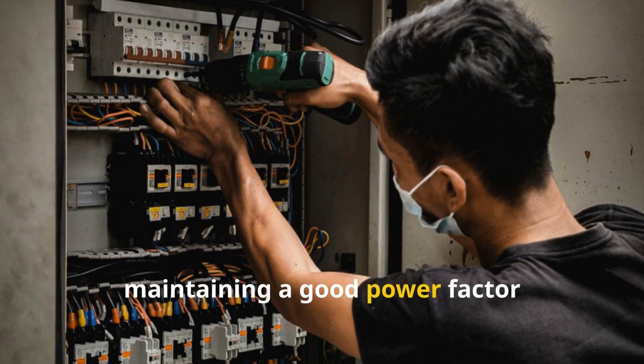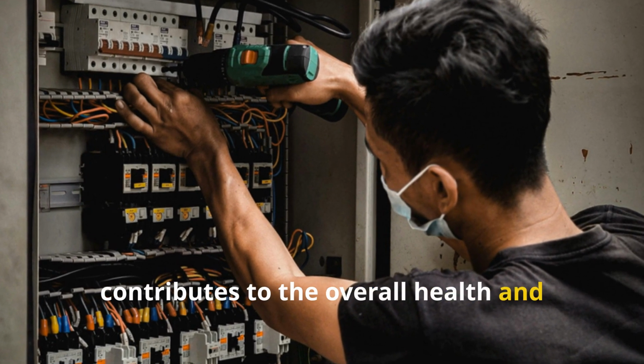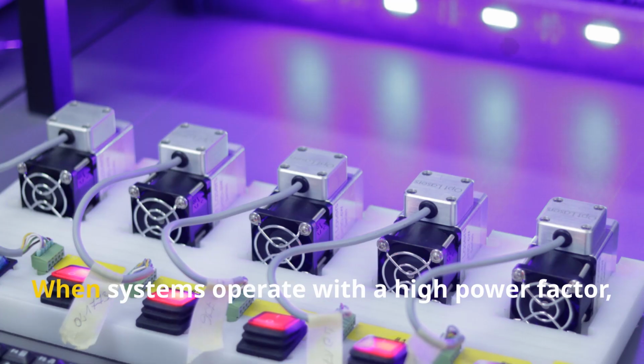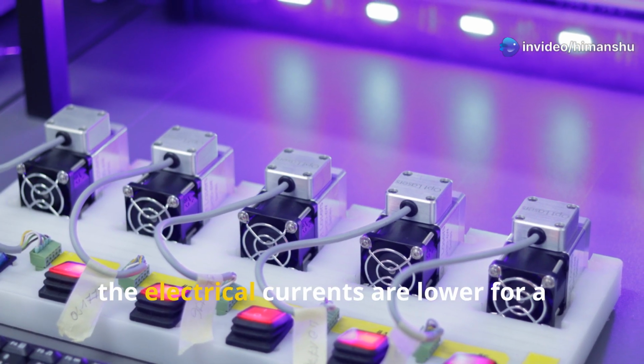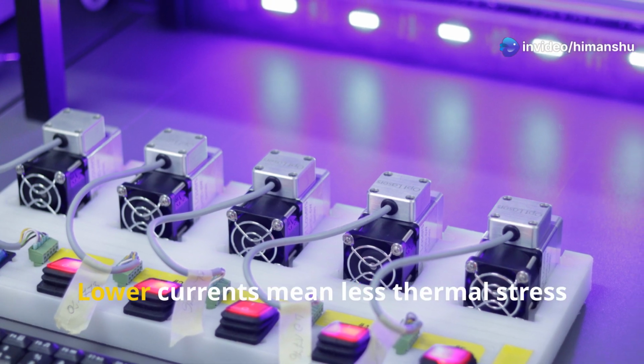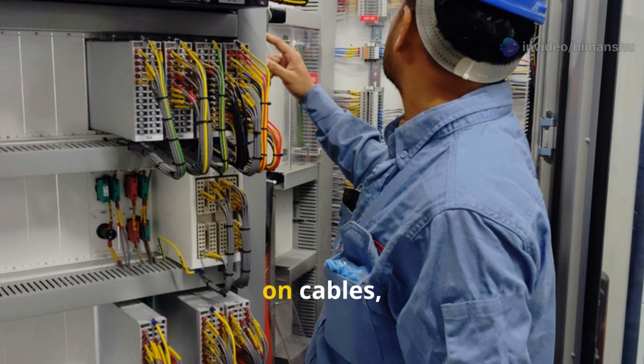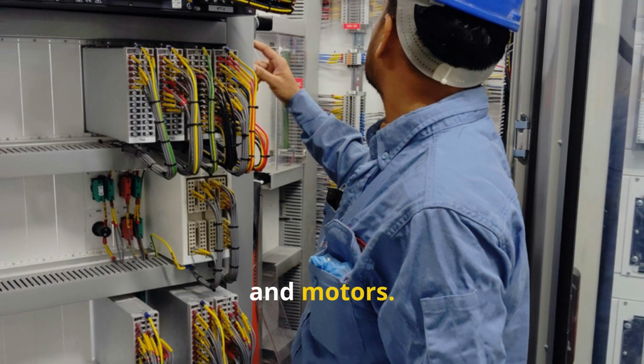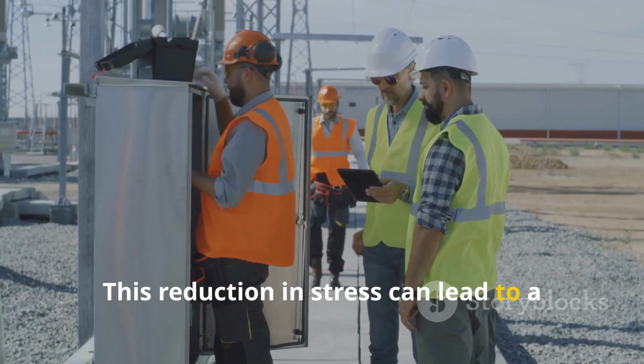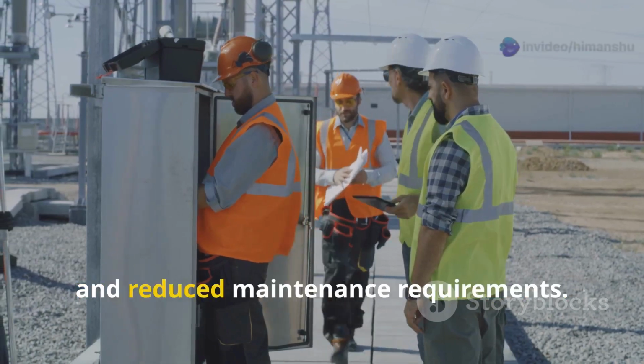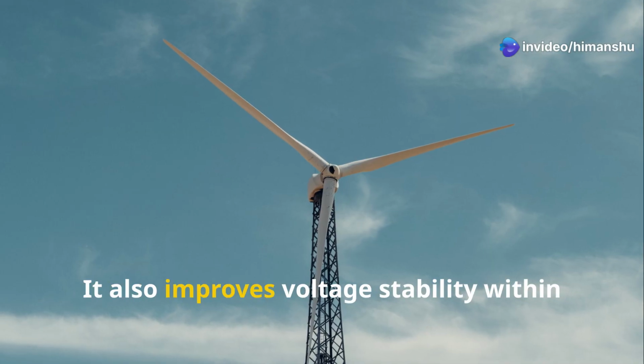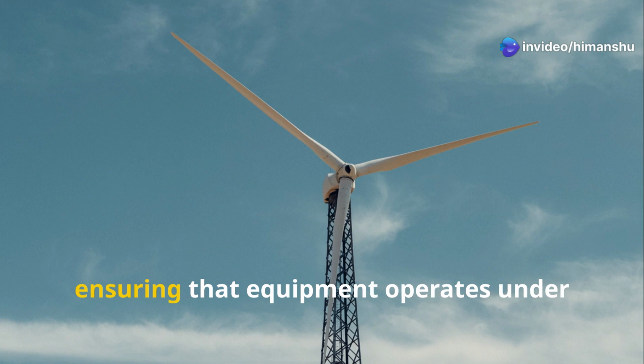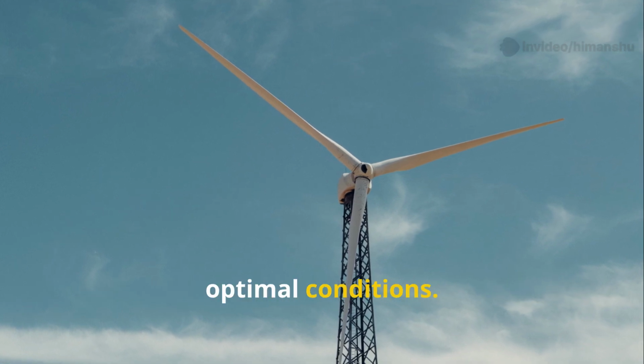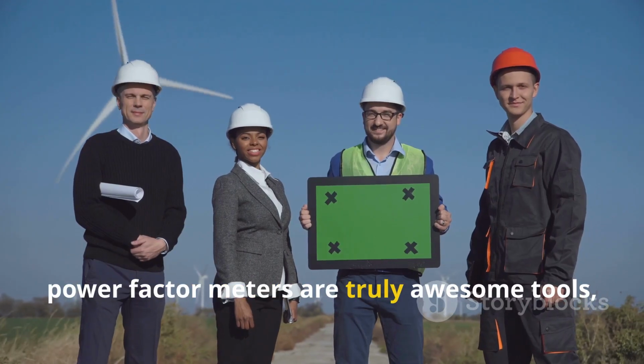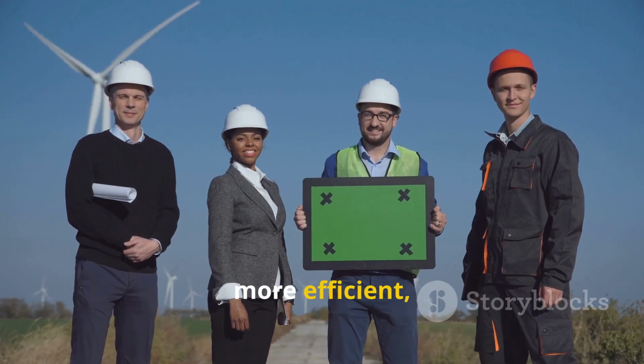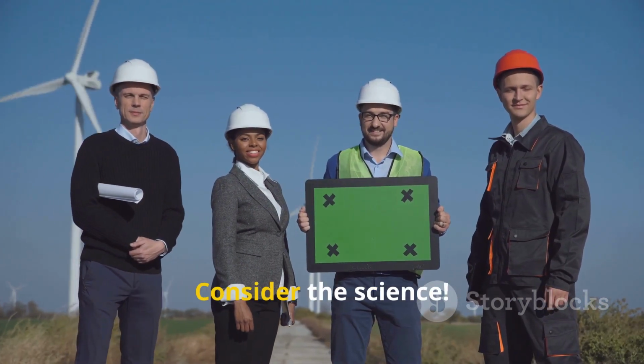Furthermore, maintaining a good power factor contributes to the overall health and longevity of electrical equipment. When systems operate with a high power factor, the electrical currents are lower for a given load. Lower currents mean less thermal stress on cables, switchgear, transformers, and motors. This reduction in stress can lead to a longer operational life for the equipment and reduced maintenance requirements. It also improves voltage stability within a facility, ensuring that equipment operates under optimal conditions. So, power factor meters are truly awesome tools helping us build a smarter, more efficient, and more sustainable electrical world. Consider the science.